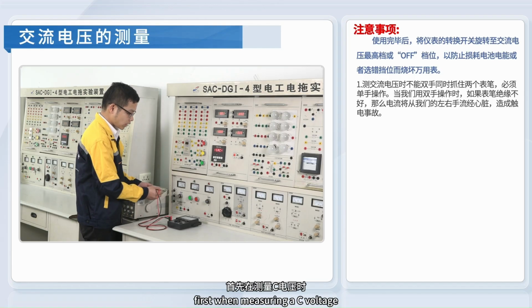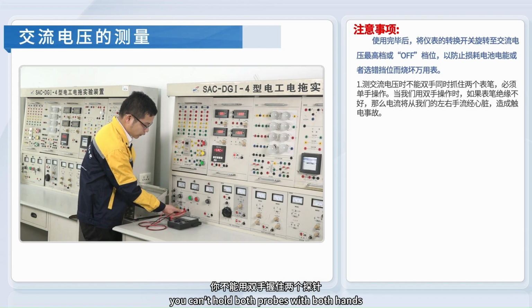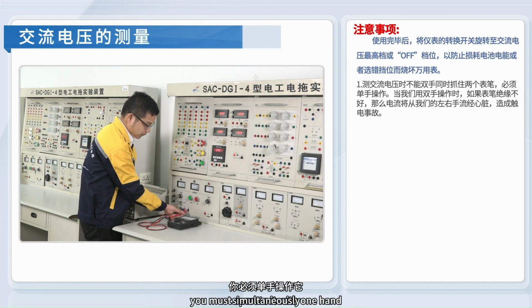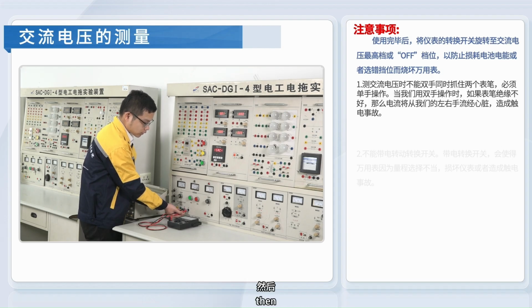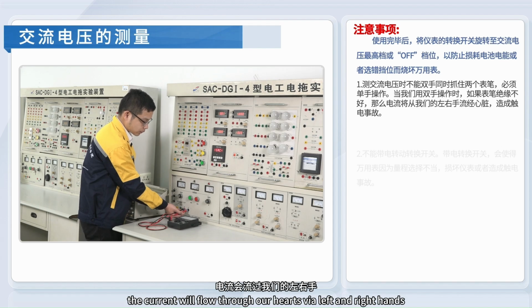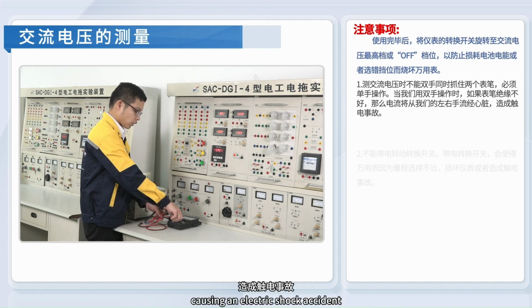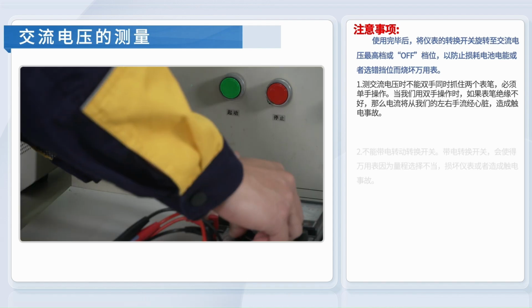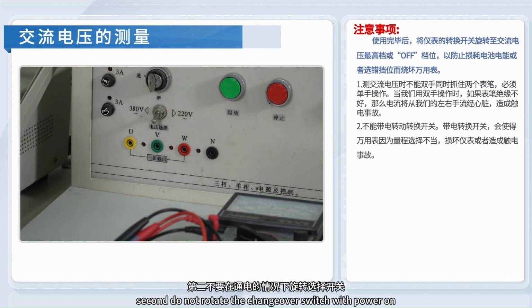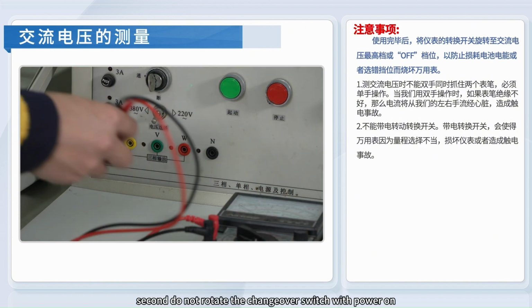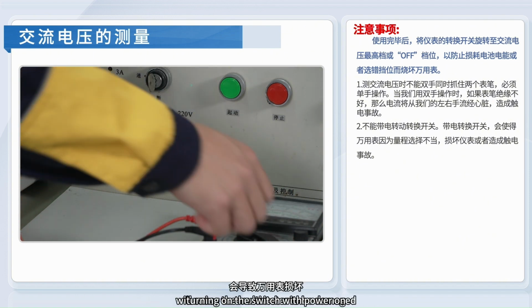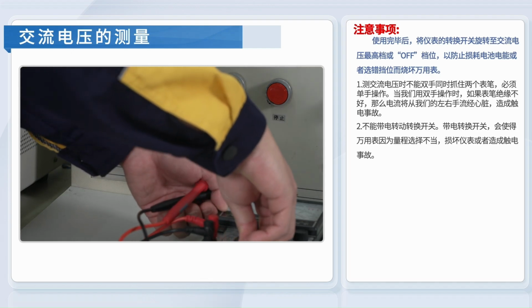First, when measuring AC voltage, you can't hold both probes with both hands simultaneously. You must operate with one hand. When we operate with both hands, if the probes are not insulated well, then the current will flow through our hearts via the left and right hands, causing an electric shock accident. Second, do not rotate the changeover switch with power on. Turning the switch with power on will cause the multimeter to be damaged.